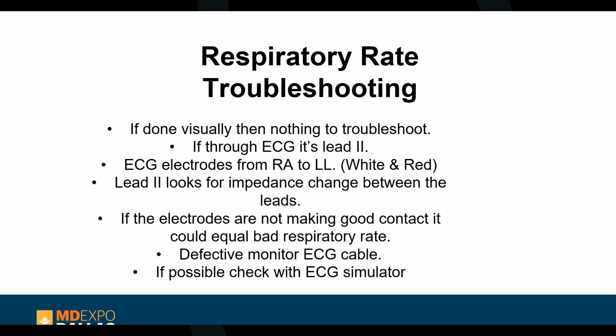So if it is ECG lead 2, if done visually, there's really nothing to troubleshoot. If it's through ECG lead 2, then I always say to start with the patient, the electrodes that are attached to the patient, and kind of work your way back to the monitor, as usually the monitor is the least amount of the problems. It's not usually going to cause a bad respiration rate. ECG lead 2 is right arm to left leg, like we talked about, and it's the white lead and the red lead for the colors.